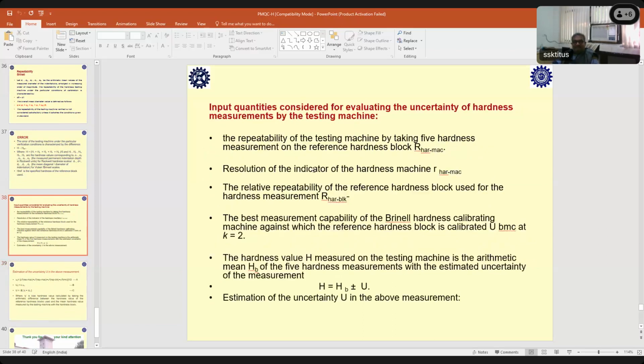So these are the major components. One is the resolution of the machine, and you have to consider the repeated measurements that you are making from your sample. So you will get the standard uncertainty from that, and your resolution, and your standard block uncertainty. These three components are very critical, and using these three components you are going to estimate the overall combined uncertainty.